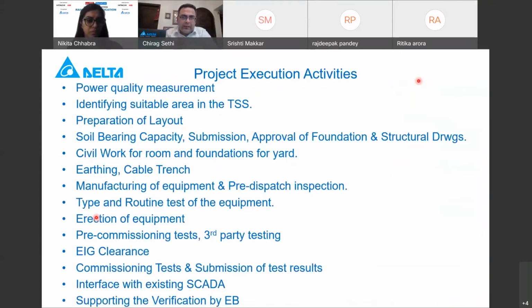What are the activities involved in this? Our activity starts right from power quality measurement to assess the exact rating of equipment required. Once there, we identify the suitable area within the substation, do the soil bearing capacity, prepare the foundations and the layouts, and the civil work, which could be either a room or a container based solution. The earth mat, cable trench, as well as the complete erection of equipment is in our scope.